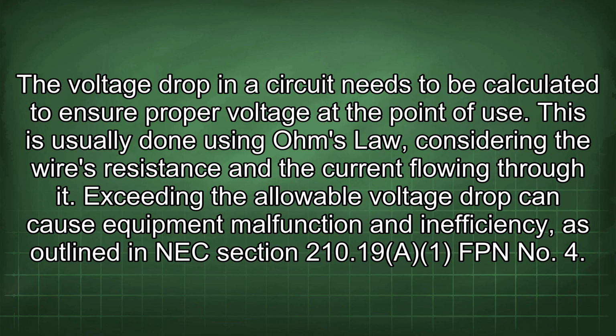The voltage drop in a circuit needs to be calculated to ensure proper voltage at the point of use. This is usually done using Ohm's law, considering the wire's resistance and the current flowing through it. Exceeding the allowable voltage drop can cause equipment malfunction and inefficiency, as outlined in NEC section 210.19A, FPN No. 4.